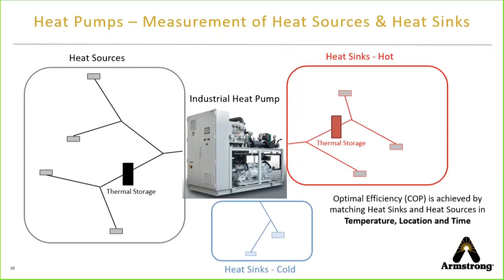We do the same thing on the heat sink side. And we need to understand and monitor the flows, the temperatures of what's going to our heat sinks on the hot side and our heat sinks on the cold side. And that's all important to monitor because that's how the optimal efficiency, that's how the COP is going to be calculated. And it's all done based on study of a given area, given portion of the plant, given processes. So the energy metering, the flow and temperatures allows us to monitor the network and to maintain its efficiency. And then we can adapt, we can replace, we can add other peripheral equipment to continue to maintain that optimal efficiency as we go through.